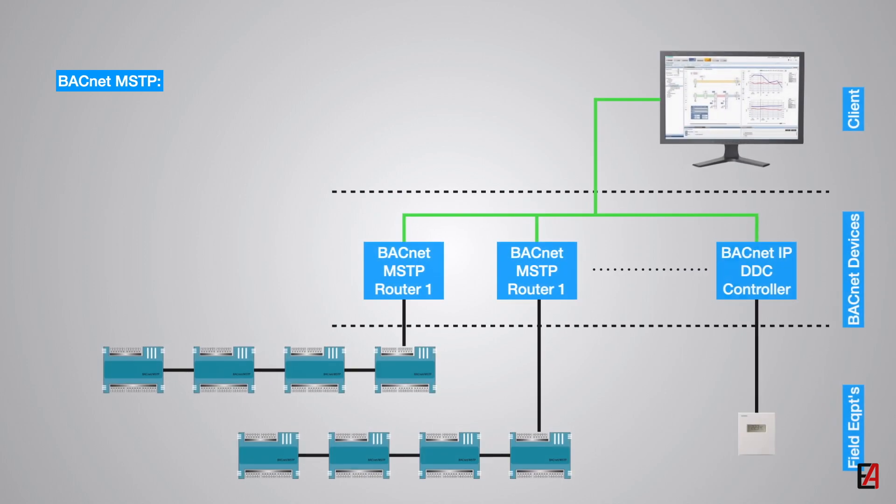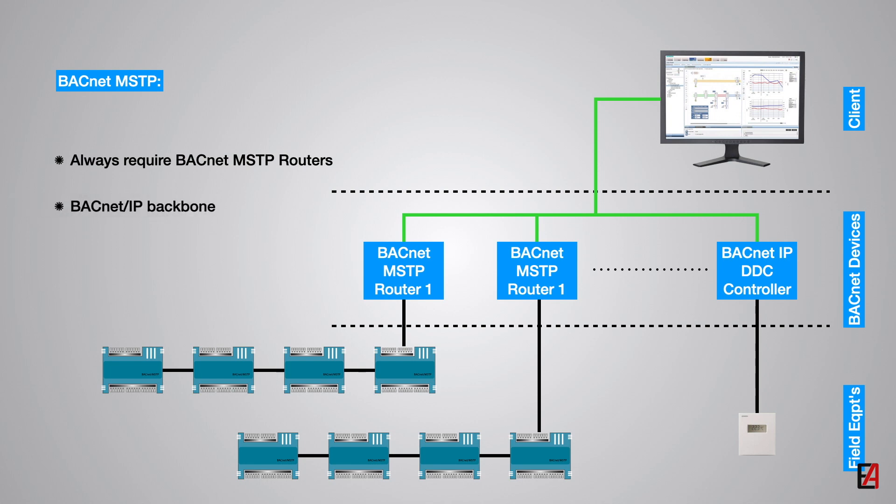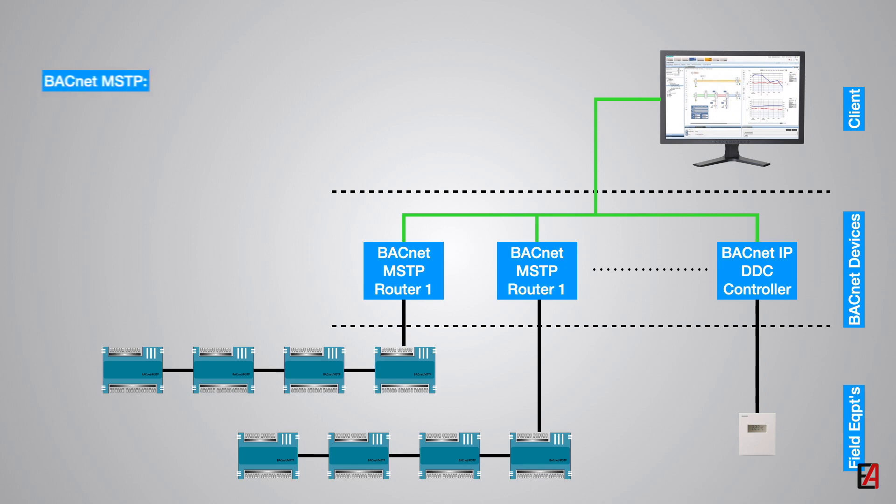Even though BACnet MSTP is officially supported by BACnet, a BACnet MSTP router is always required on the network to connect the MSTP devices to the management system. The router converts BACnet MSTP to BACnet IP backbone, which is the preferred communication protocol for the BMS system.